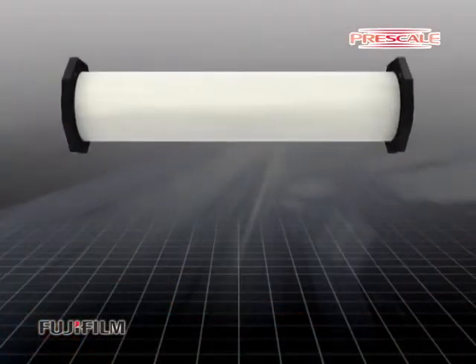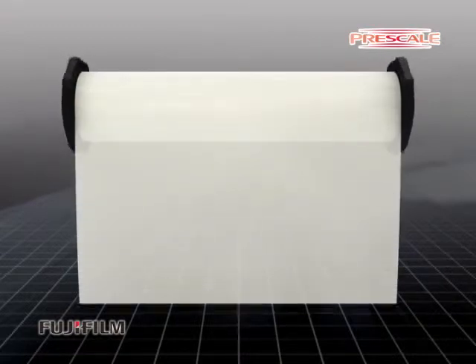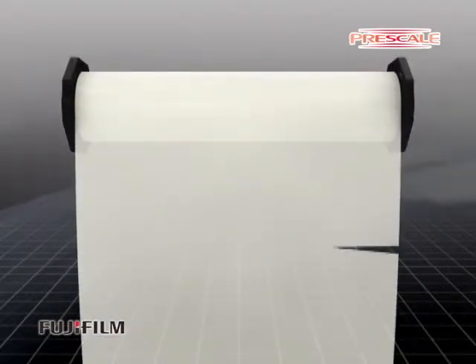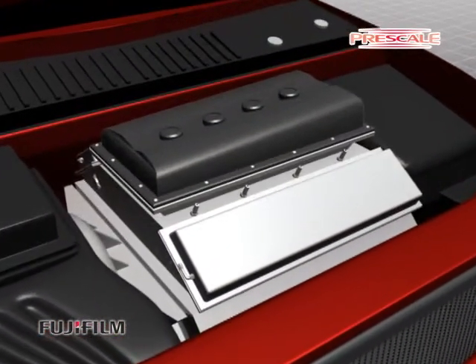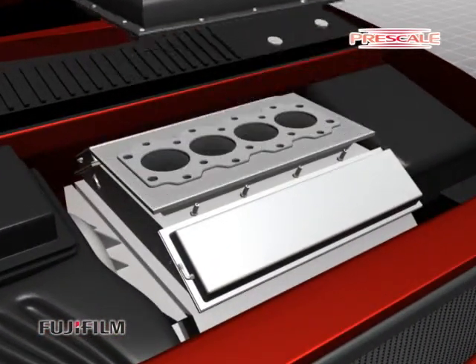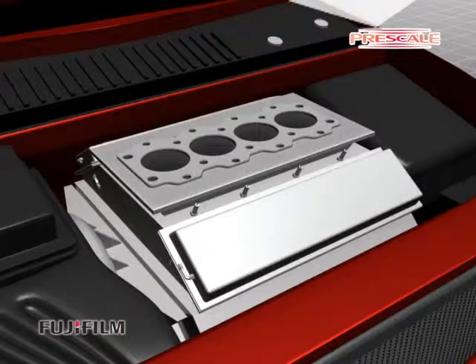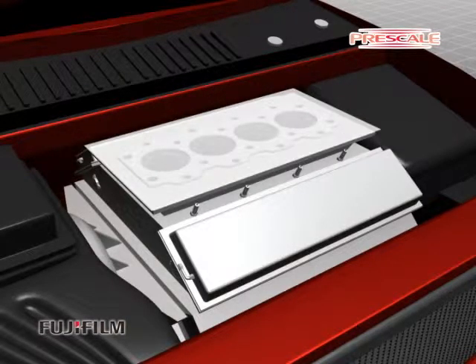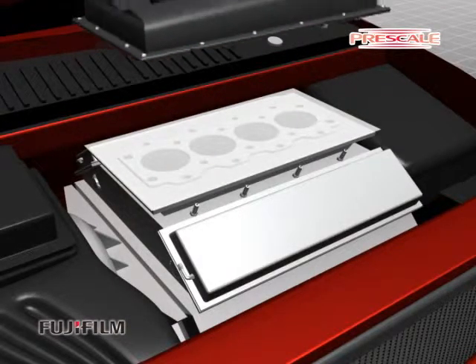To do this, cut Prescale a little bit larger than the exact gasket size to be measured. Set the piece of Prescale onto the actual gasket position and apply the prescribed torque to the bolts.